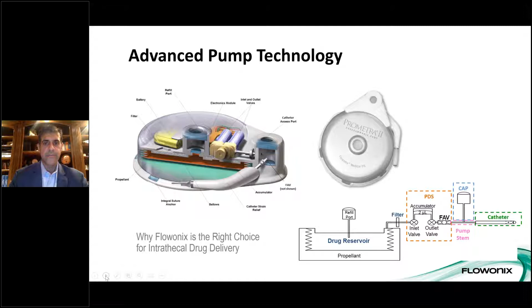Let's look at the flow activated valve. This is certainly an update to the Prometra 2 pump as it has evolved from the Prometra 1 pump. To note, the Prometra 2 pump is MRI conditional up to 1.5 Tesla. Basically, the flow activated valve will deploy in the event of a high flow rate, such as during an MRI, basically shutting off or blocking flow of any drug from the reservoir to the patient.